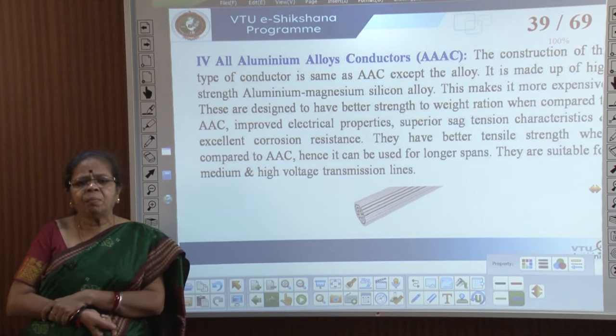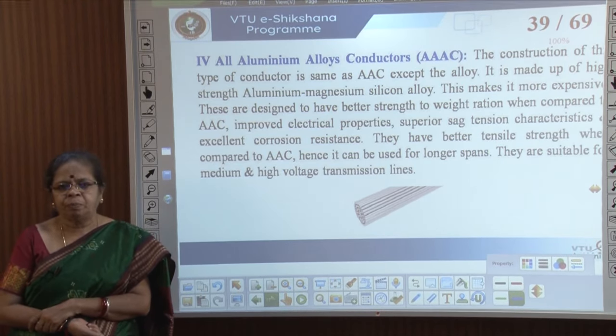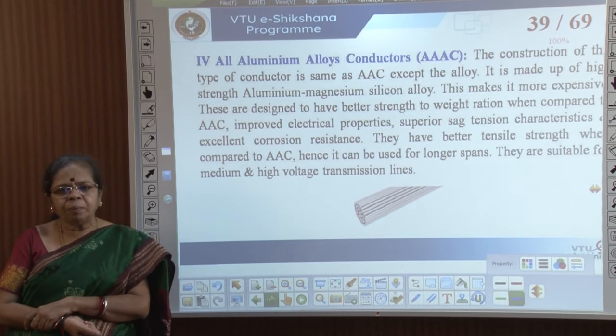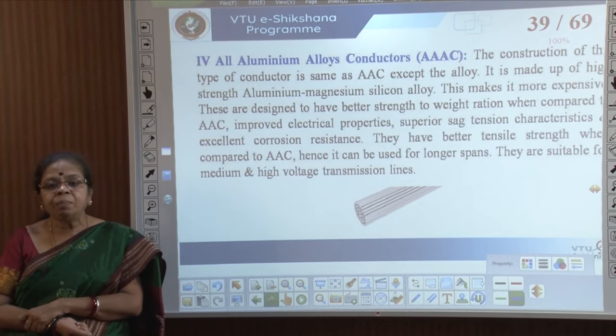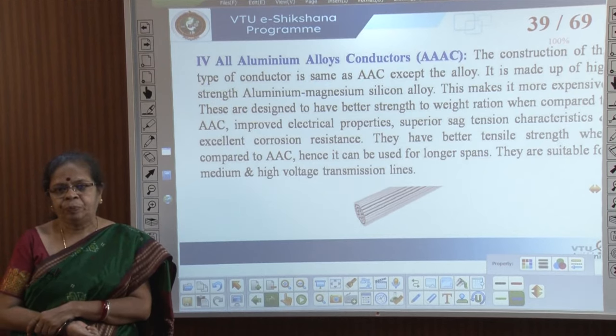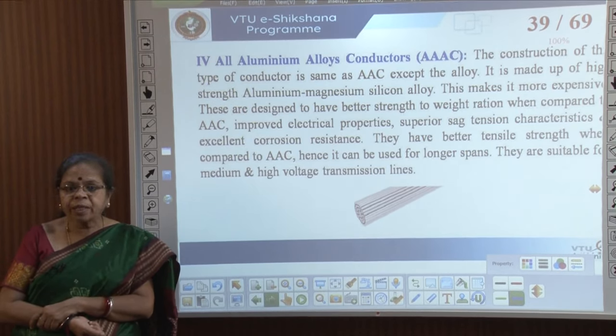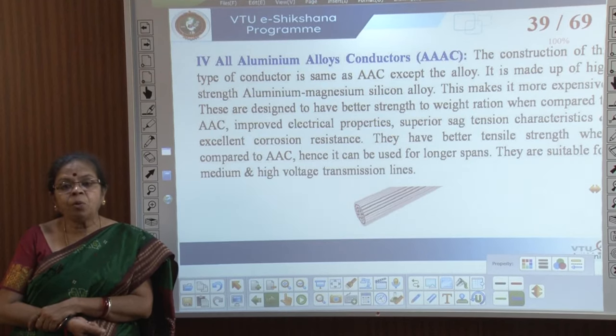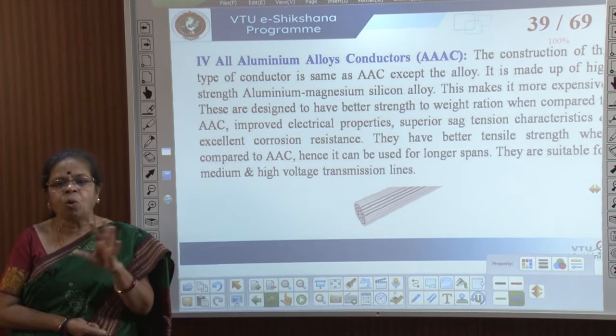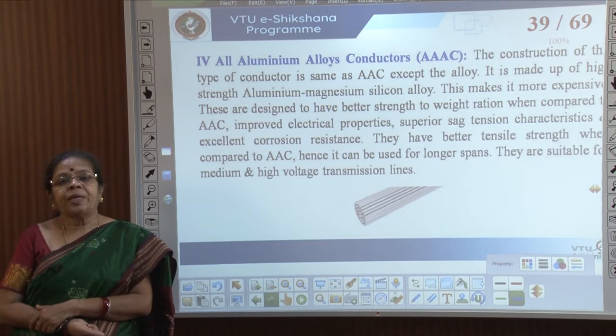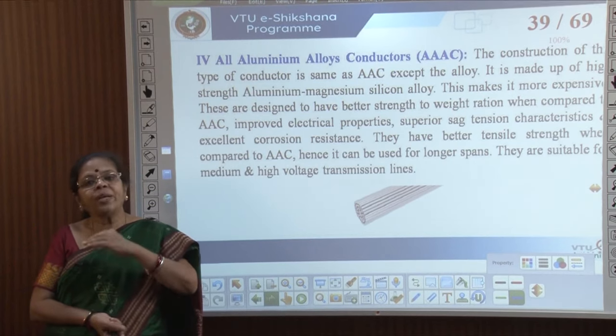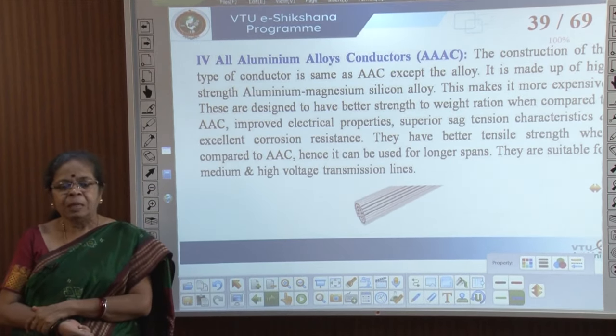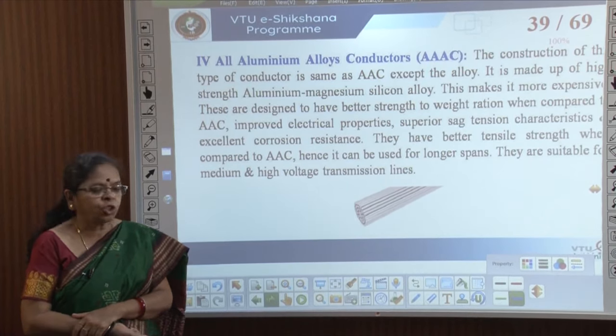Next, All Aluminium Alloy Conductors, or AAAC, are similar to AAC except the alloy used is a high-strength aluminium-magnesium-silicon alloy. It is more expensive but can be designed to have a better strength-to-weight ratio than all aluminium conductors. It has improved electrical properties and reduced sag compared to pure aluminium, so it can be used for longer spans and is suitable for medium and high voltage lines.